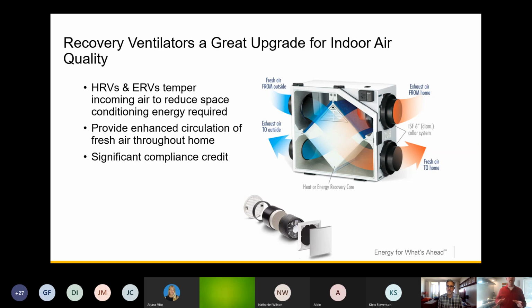More importantly, you duct the fresh air throughout your house through little 4-inch ducts, pumping fresh air behind closed bedroom doors at night. I've got an exhaust in the kitchen and bathrooms, continuously removing stale air from the bathrooms. If you provide 20 CFM continuous in your bathrooms, you don't need the bathroom vent fan anymore. So with the HRV, I was able to vault the ceiling in the ADU and not install a bathroom vent fan. There's significant compliance credit due to the energy savings of these.